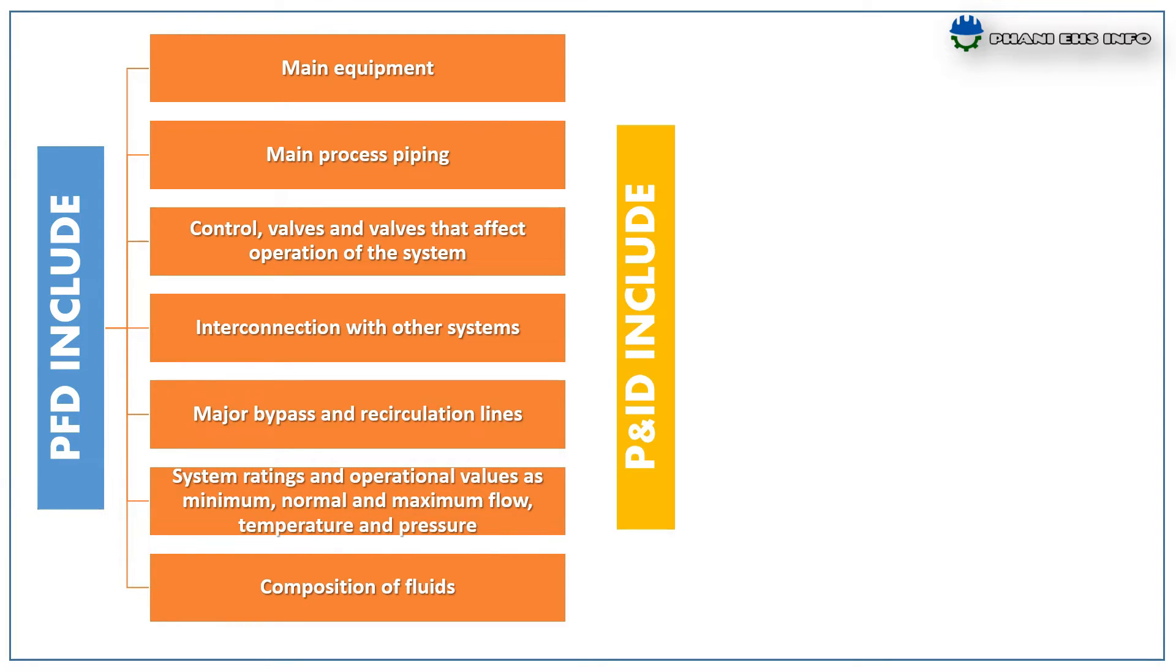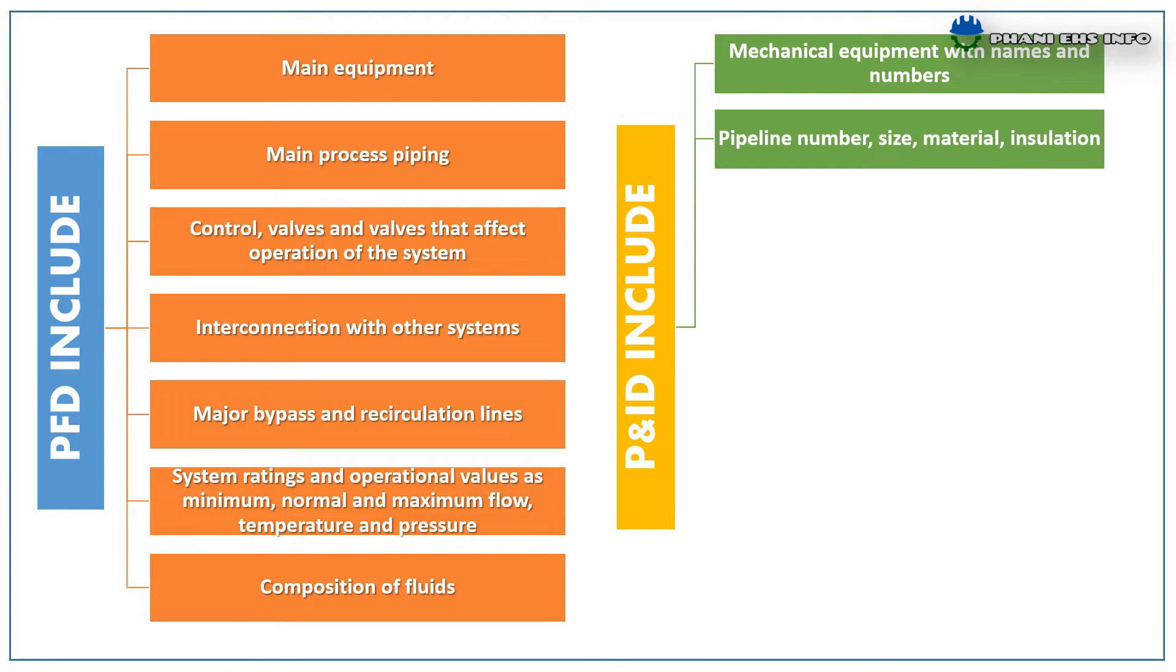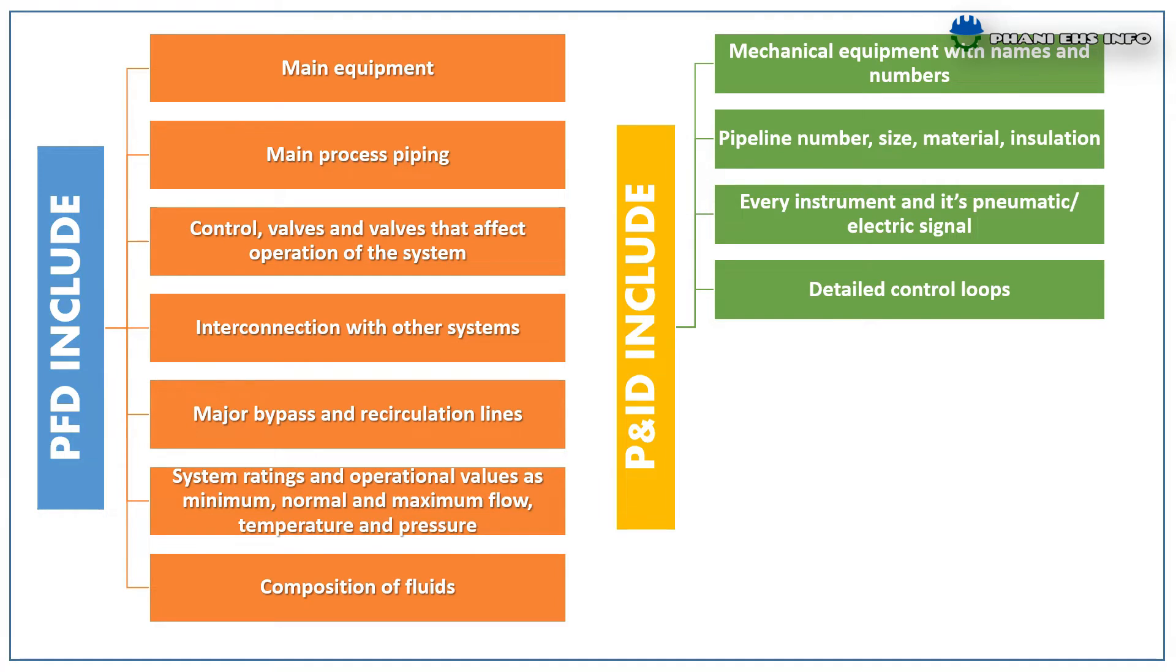And in P&ID include mechanical equipment with name and numbers, pipeline number, size, material, insulation, ventilation, every instrument and its pneumatic or electrical signal, detailed control loops, utility lines, drain and vent lines, sampling lines, etc.